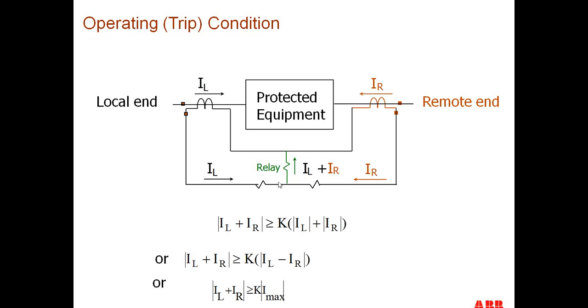So now we have a restraint winding and also an operate winding. Now we can write equations for the operate current versus restraint current. We always want the operate quantity, which is in almost all cases IL plus IR, to be greater than our restraint current. Our restraint current can be described in several different ways, used in different relay systems. One possible method is K times the absolute value of IL plus the absolute value of IR.